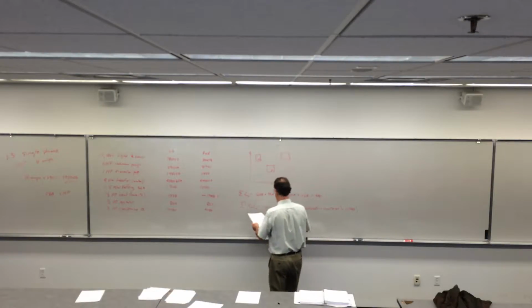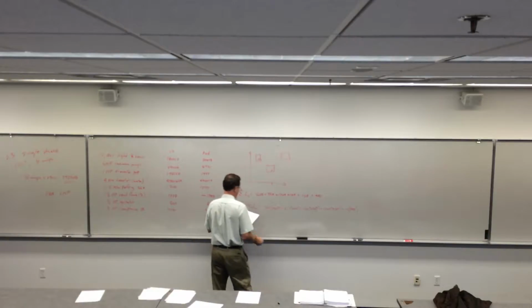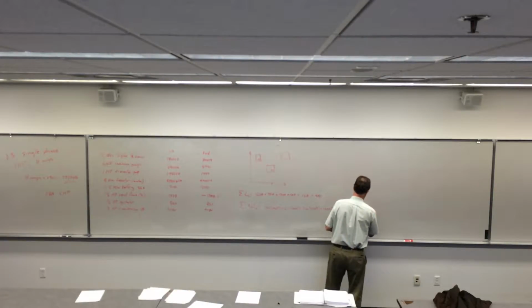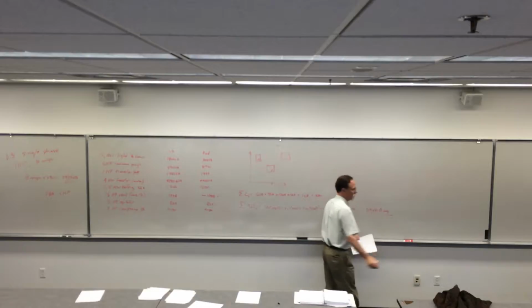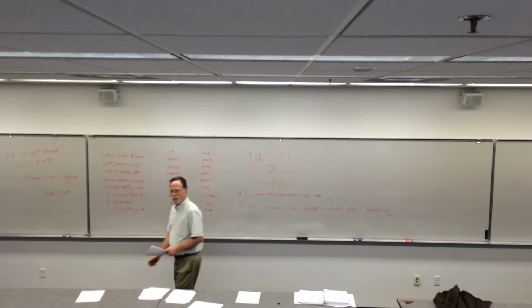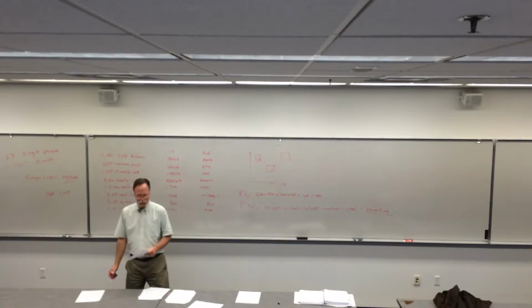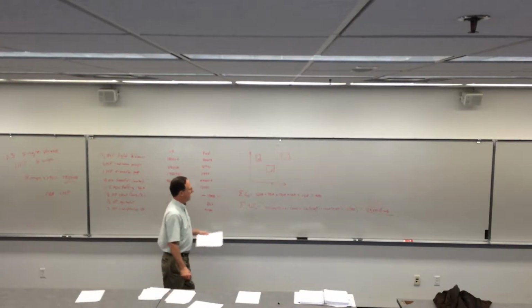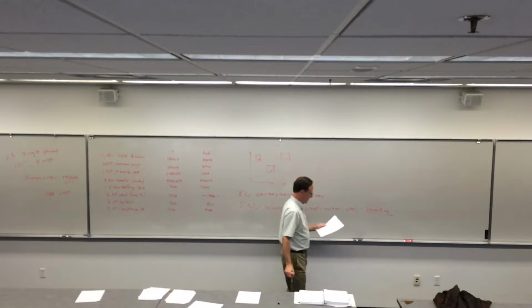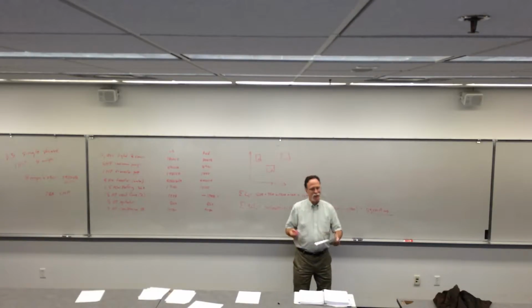So you end up with that whole thing, and you come up with a number which is actually foot amps. 84,750 foot amps. Only in agricultural electrical could you come up with a set of units called foot amps. You know, never mind, you just divide them through. This is amps, divide that through, and you get the distance to the centroid, so to speak.